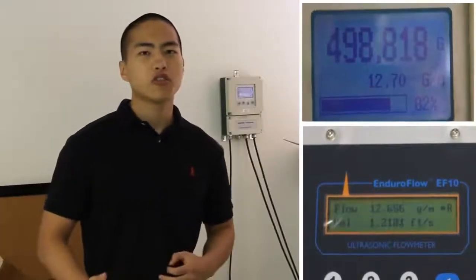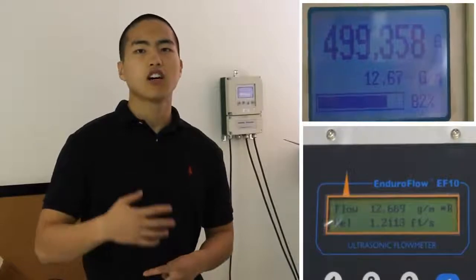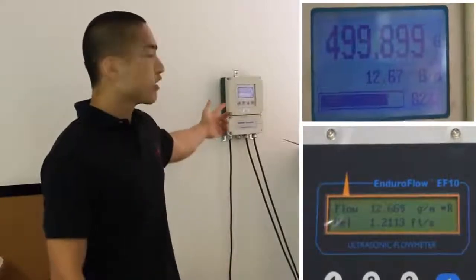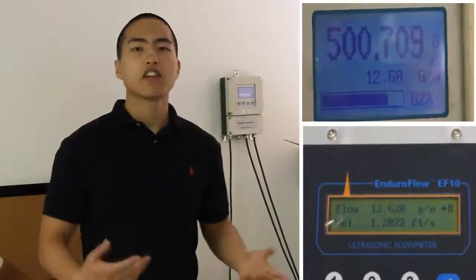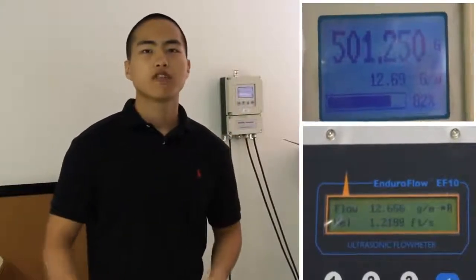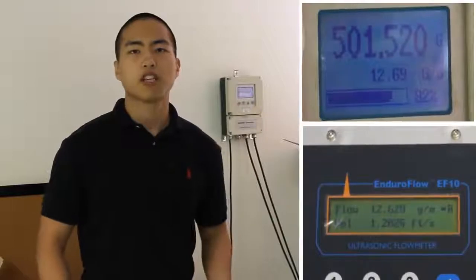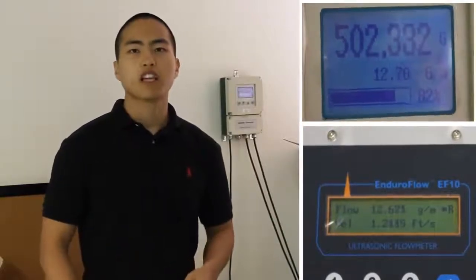Now we're going to have the shot showing you the comparison between the flow rate on our flow meter and the flow rate shown on the standard mag meter. And as you can see, the difference is always within 1%. So our flow meter is extremely accurate.